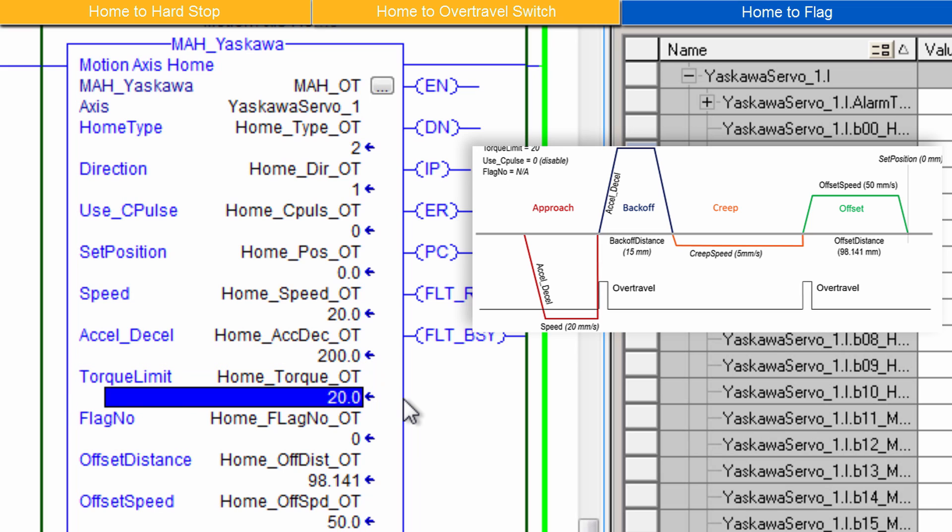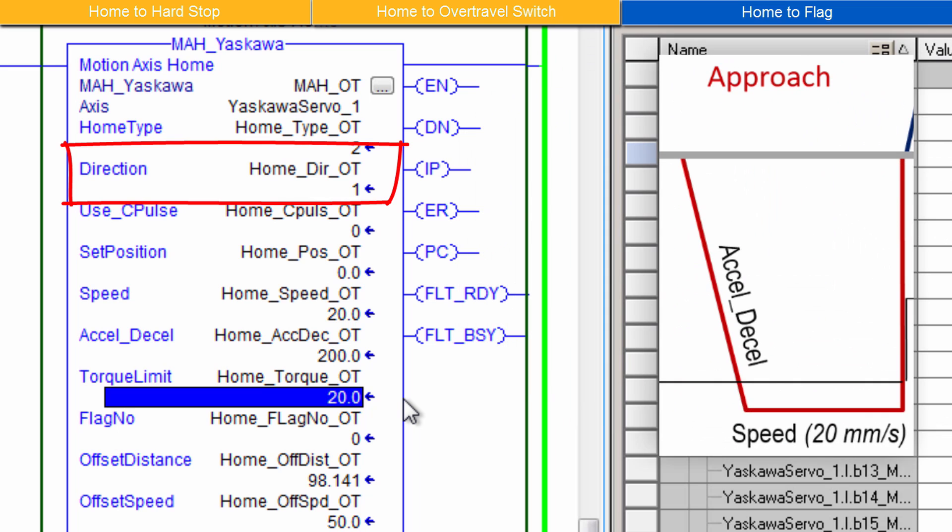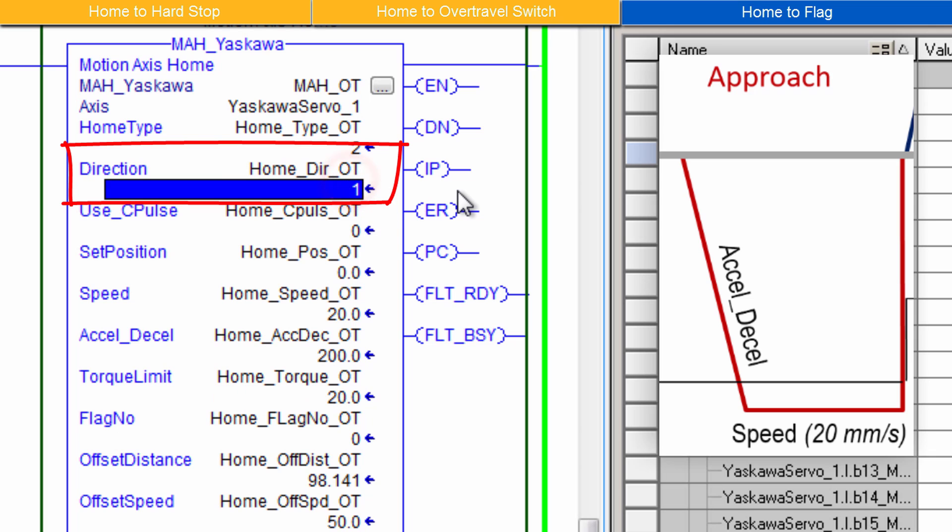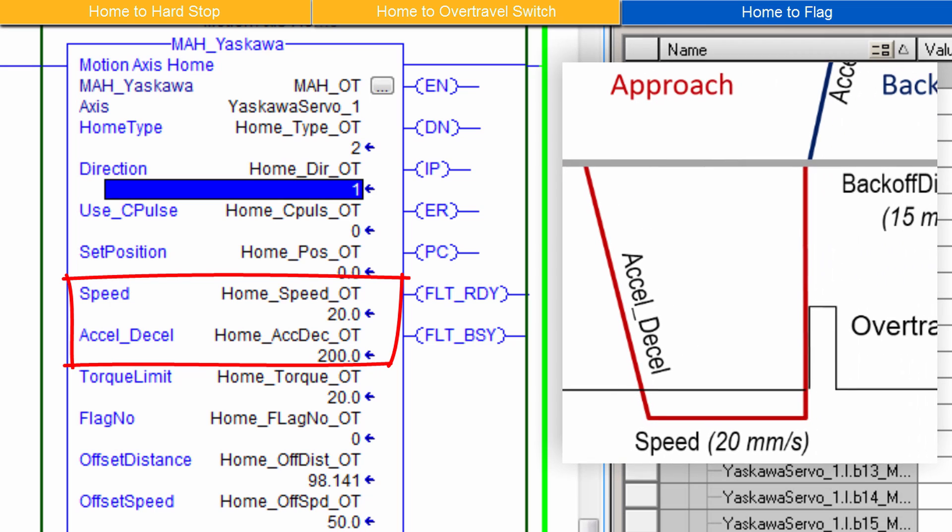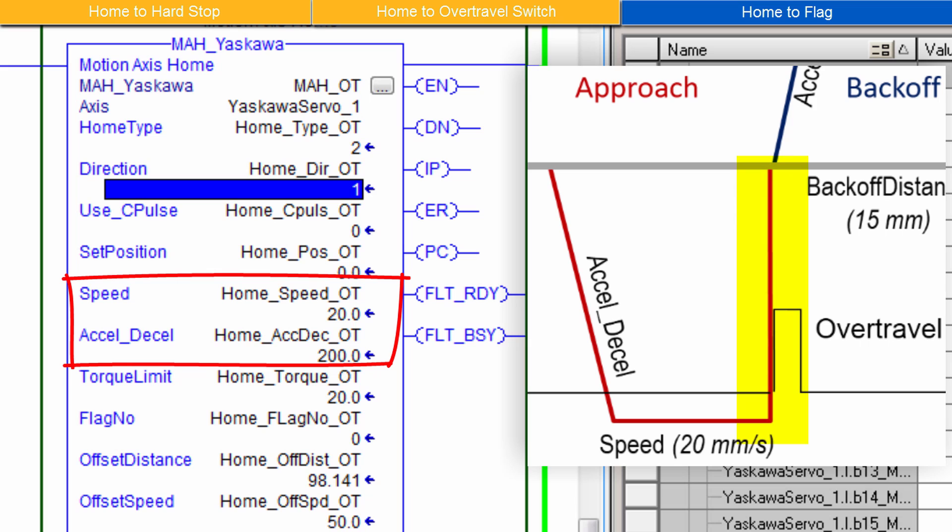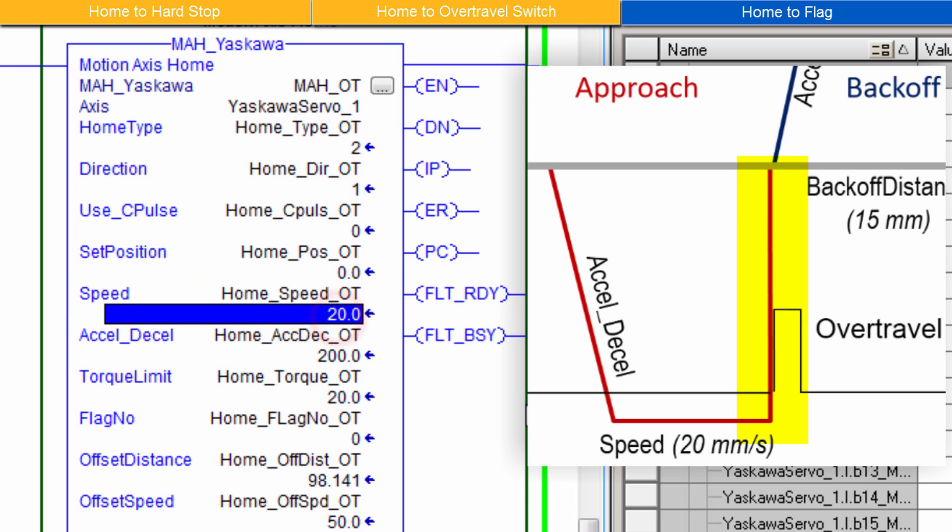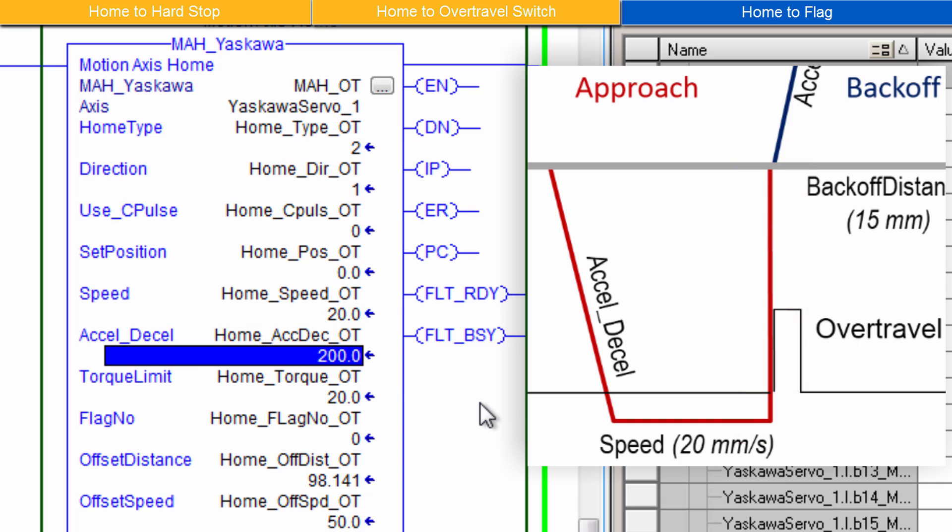For Homing Type 2 to Over Travels, if the motor torque ever reaches this percentage of rated torque, homing will be cancelled and Axis Fault Code 3, which is called Torque Limit Exceeded, will be displayed in the Alarm text. Direction applies to the Initial Approach Move. I'll set it to move to the negative over travel in the reverse direction, which is a setting of 1. Set an appropriate speed and acceleration for the Approach Move. And keep in mind the system will stop abruptly at the over travel sensor, so don't set the speed too high. I'll set the speed to 20 millimeters per second and Accel_Decel to 200 millimeters per second squared.